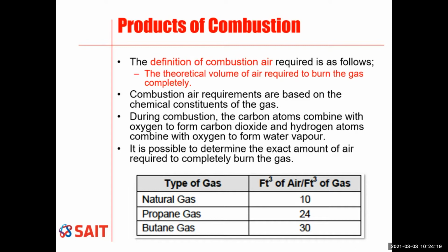So type of gas, natural gas, 1 cubic foot of gas, 10 cubic feet of air. Propane gas, 1 cubic foot of propane, 24 cubic feet of air. We went through this already. So any questions on this? Just shout out if you do have something.